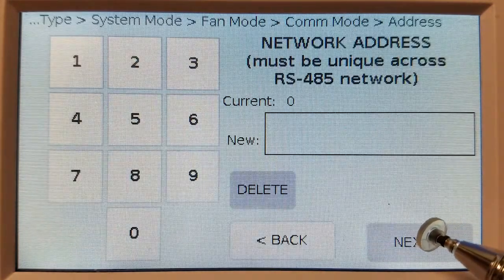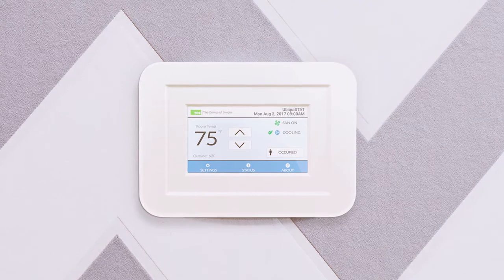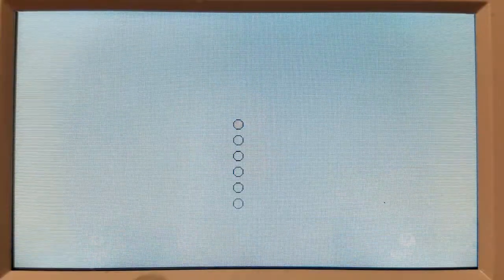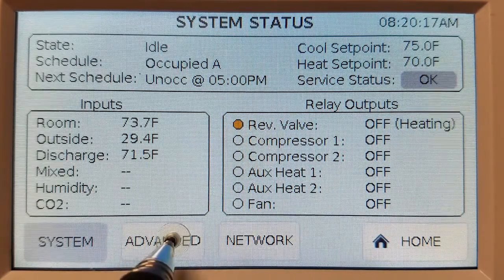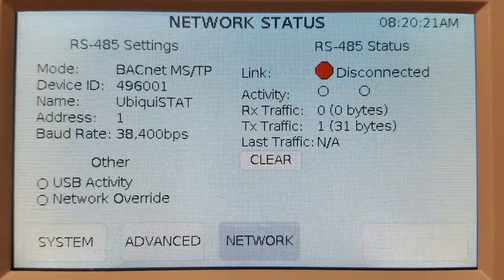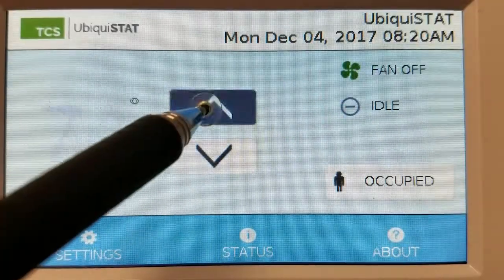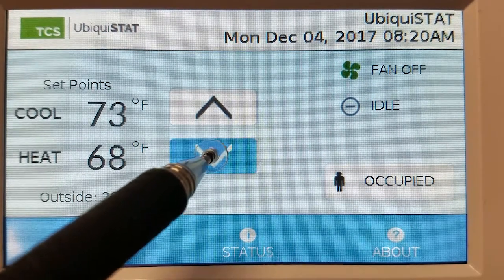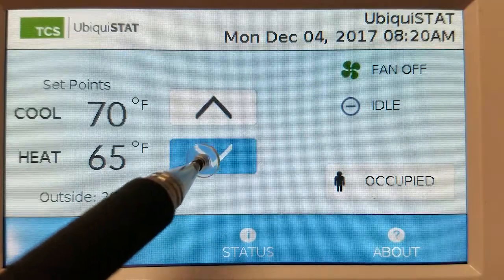Once you complete the startup wizard, your Ubiquistat is ready to communicate on a network, be commissioned, and programmed with set points and schedules. Three status screens show the current values and status of all inputs and outputs, as well as network activity, settings, and network status. Users can easily change the set points and still maintain the deadbands you've established, and that set point change can be limited to just a degree or two if you choose.